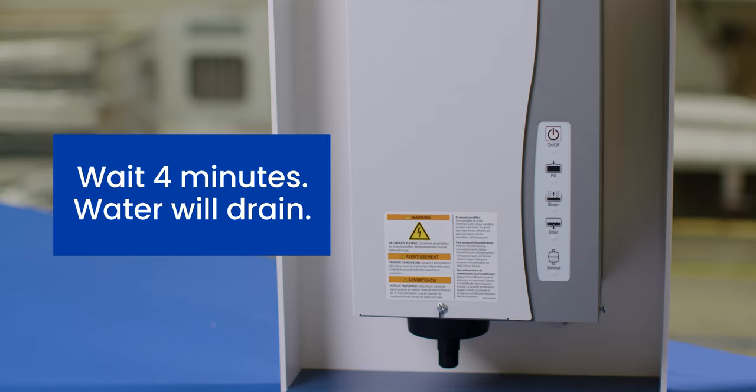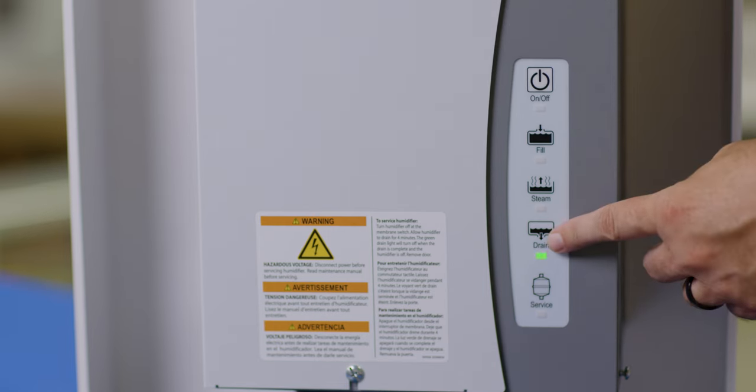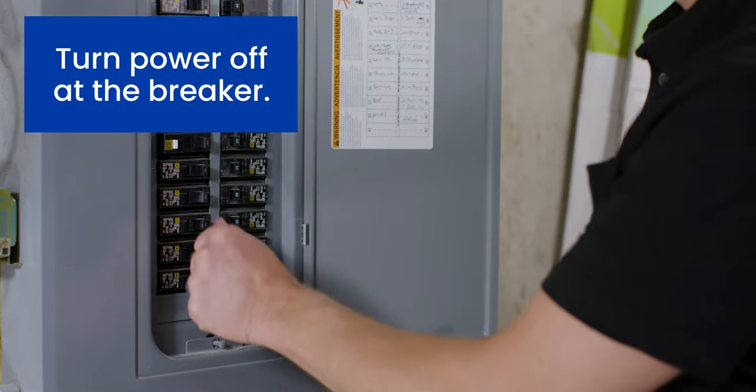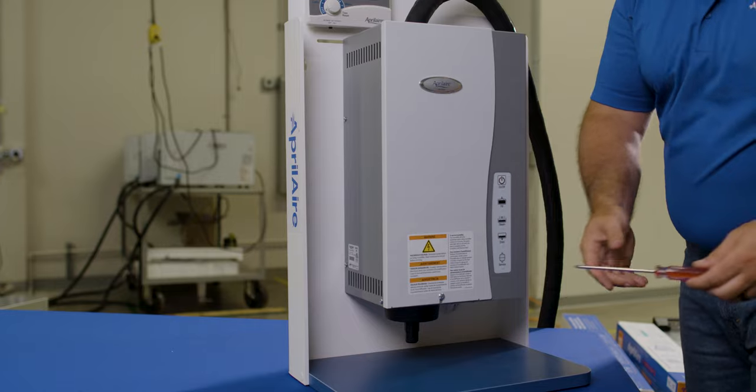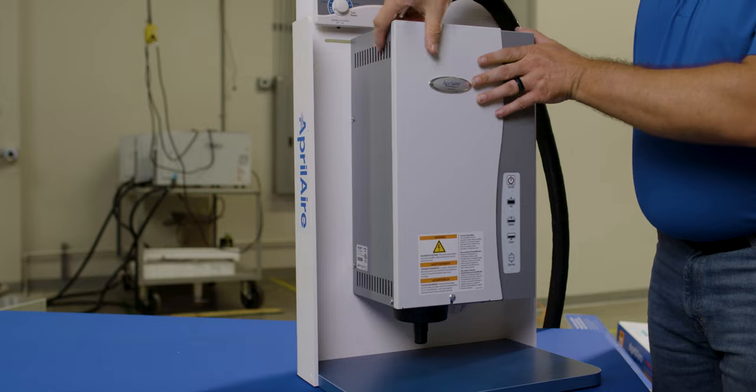Wait four minutes to make sure all the water is out of the unit. After that four minutes, the green LED will stop flashing and both valves will shut. Next, cut the power to the unit by turning it off at the breaker. Now you can take the cover off the steam humidifier. Loosen the screws at the bottom and slide the cover off.